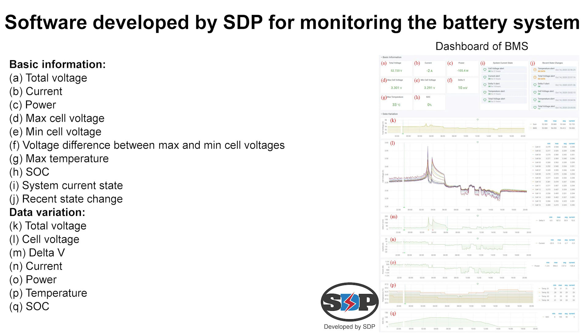Let's see a real case showing the power of BMS. With the well-designed BMS, the over-voltage condition during charge has been controlled and the battery system works in a safe region. When the highest cell voltage is larger than the over-cell voltage protection value, OCVP, which is 3.600 volt, the charge relay is turned off by the BMS and the highest cell voltage won't go over the OCVP value in the figure.